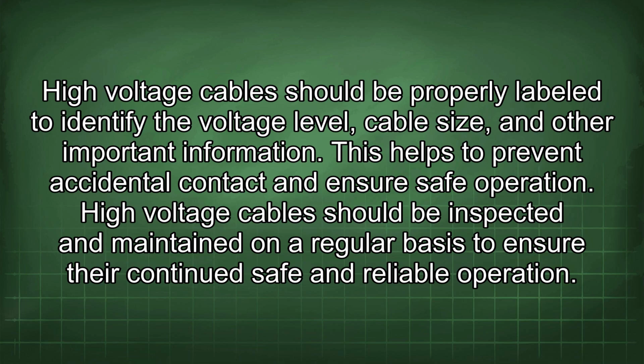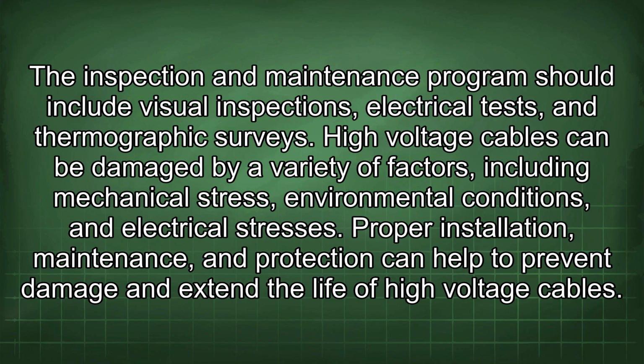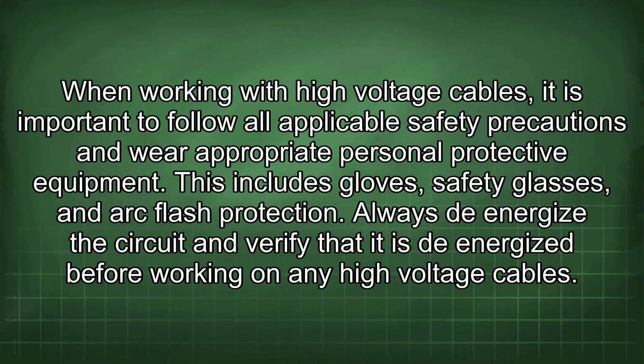High voltage cables should be inspected and maintained on a regular basis to ensure their continued safe and reliable operation. The inspection and maintenance program should include visual inspections, electrical tests, and thermographic surveys. High voltage cables can be damaged by a variety of factors, including mechanical stress, environmental conditions, and electrical stresses. Proper installation, maintenance, and protection can help to prevent damage and extend the life of high voltage cables. When working with high voltage cables, it is important to follow all applicable safety precautions and wear appropriate personal protective equipment. This includes gloves, safety glasses, and arc flash protection.